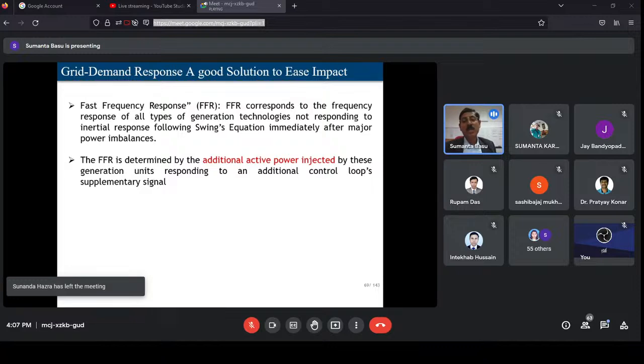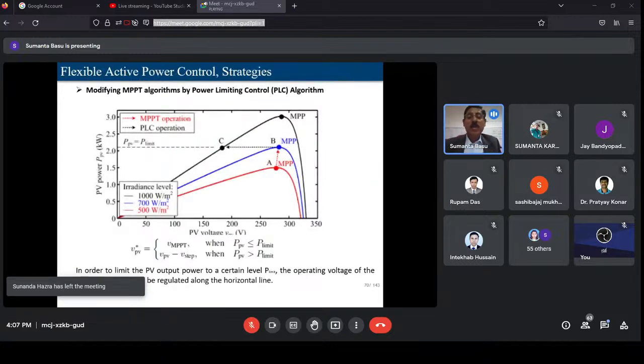35 seconds area-wise. But maybe in a particular control area, depending on the size of that control area, it varies from 5 to 30 seconds, based on the control area's capacity, the control area's location, the interconnections with other control areas, etc. So FFR is the need of the hour, which can only be supported by renewable energies. Now most of the renewable energy we talk about is solar PV.